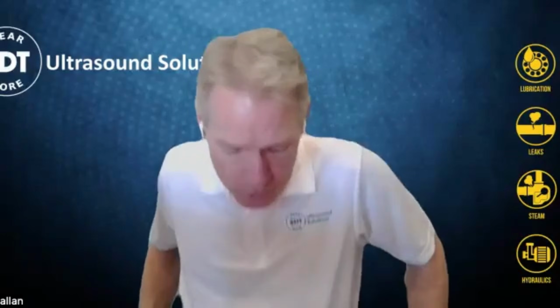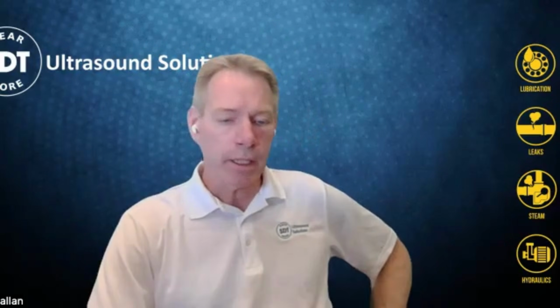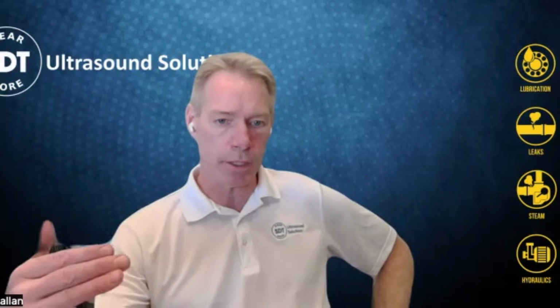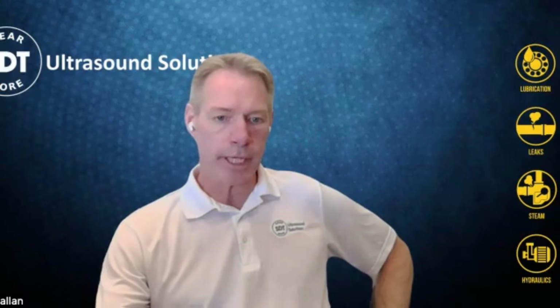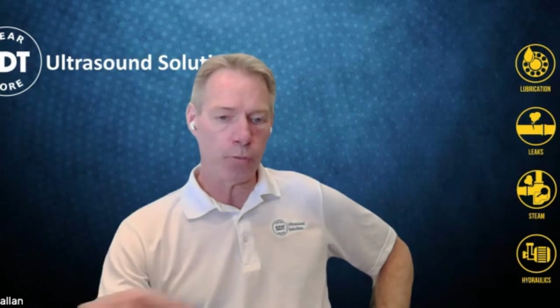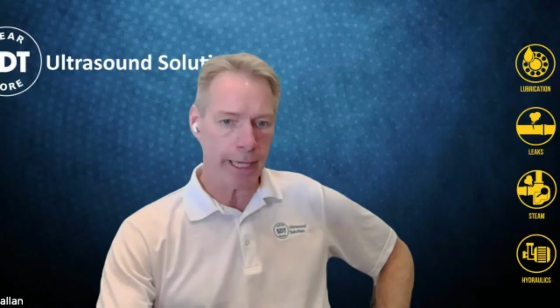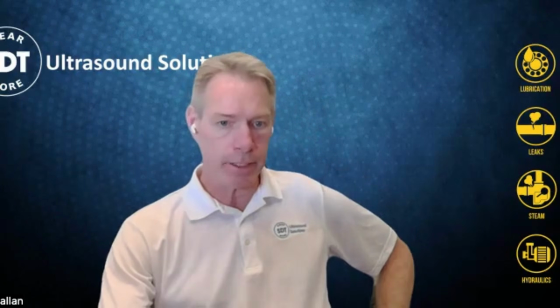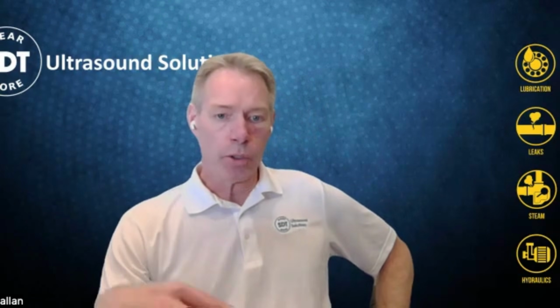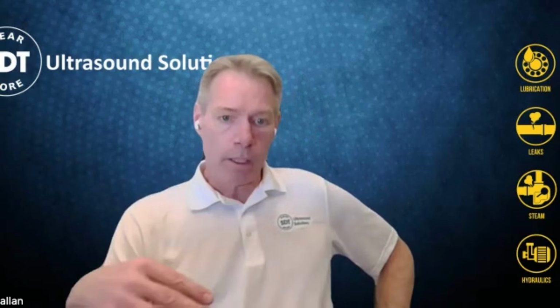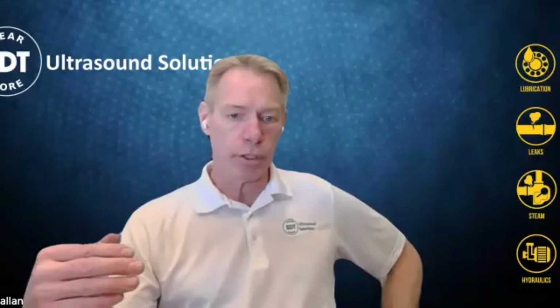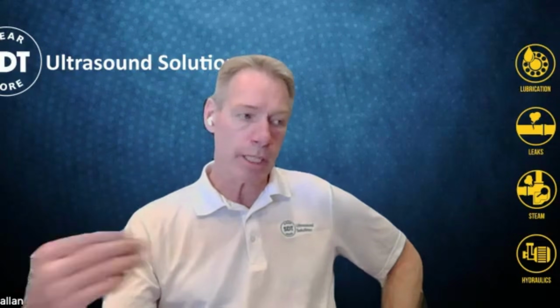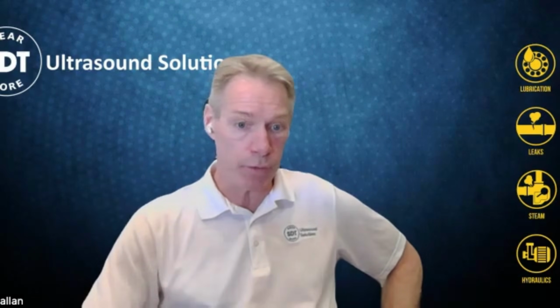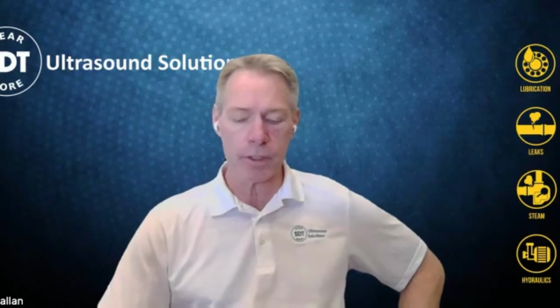Yeah, so to answer that question, let me just start by making a statement, and that is that the higher the frequency of your condition monitoring, the sooner you're going to detect problems. So if we're only relying on vibration analysis, which is typically 10 kilohertz or lower, you're going to find problems, but you're going to find them later in the P to F curve. The higher you go in the frequency, the earlier the indication of a conditional change. And that's why we say ultrasound is kind of your first line of defense against asset failures.